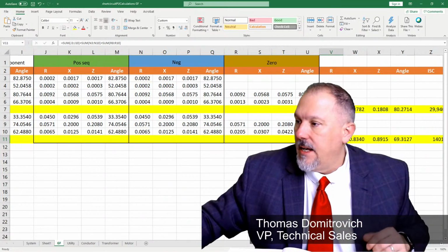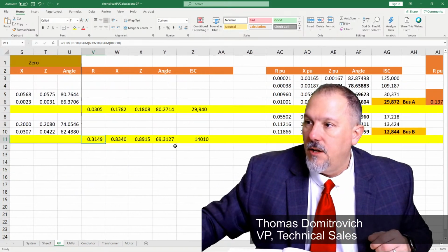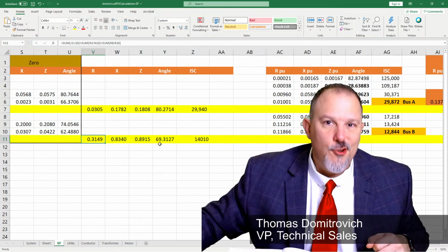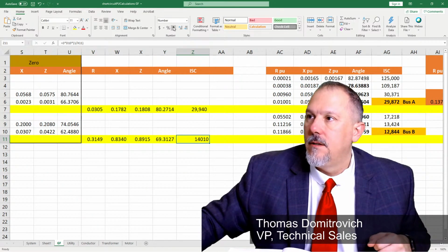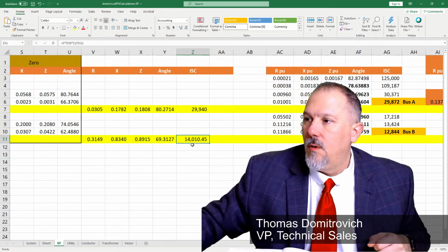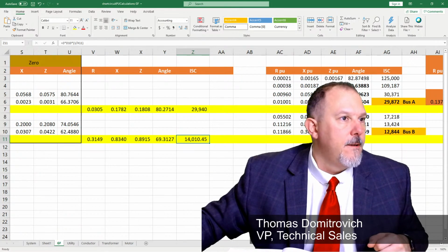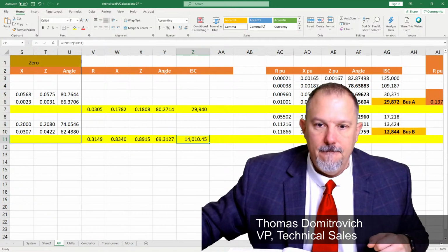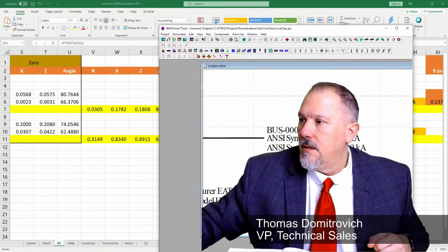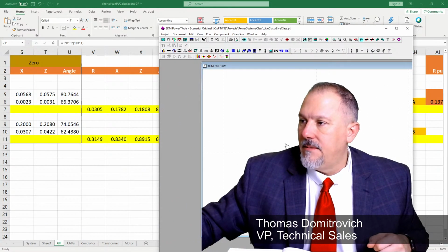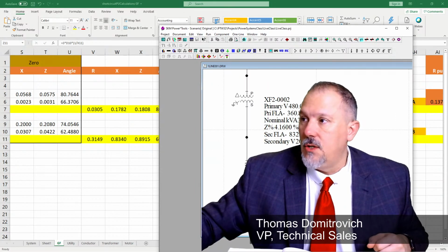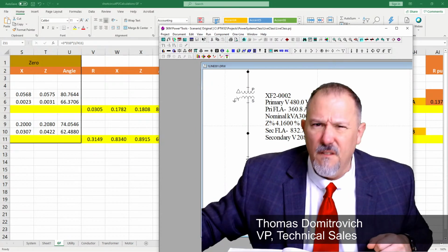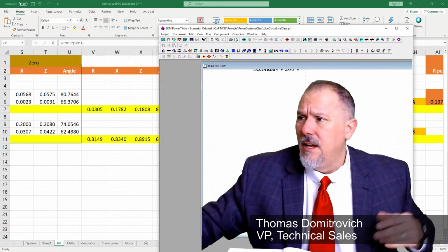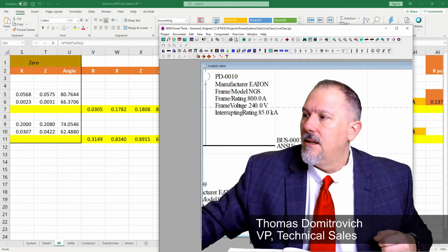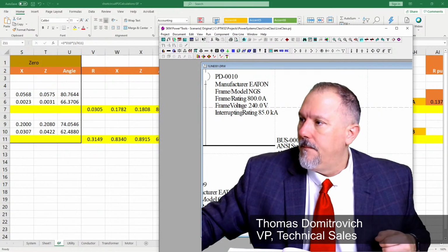Now, if I look at my calculated value in my spreadsheet, you can format that: 14,010.45. Let's go down to that second bus. There's my T2. There's that delta. Love those deltas because they just block those ground fault currents. And look at this, 14...